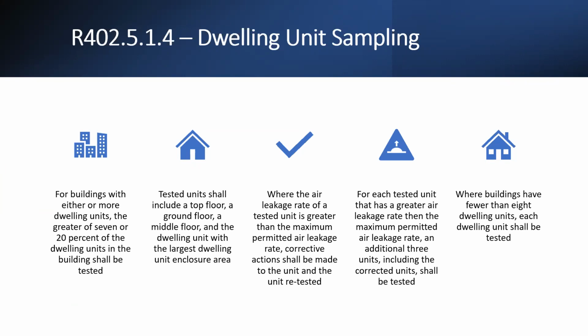So there is, and I like to see that this came from the commercial side of this, but if you have what's considered a multifamily dwelling unit and it's residential because it's 3 stories or less, they've brought into this a dwelling sampling protocol. So for buildings with 8 or more dwelling units, you need to test the greater of 7 or 20% of the dwellings.